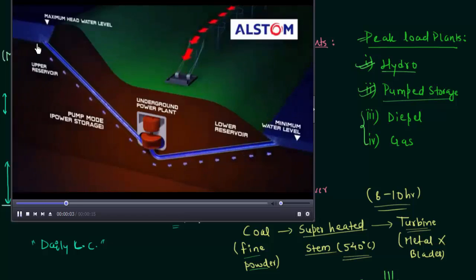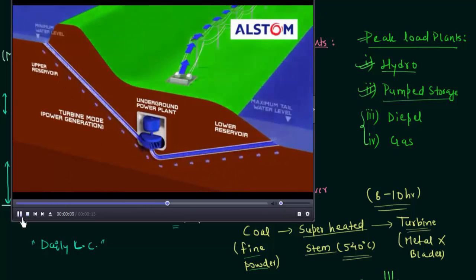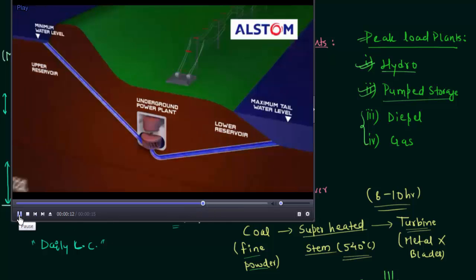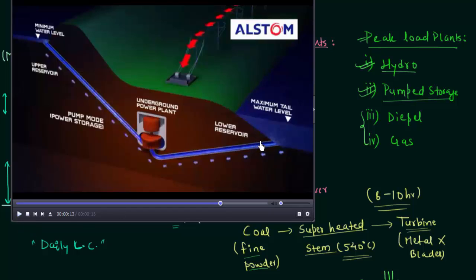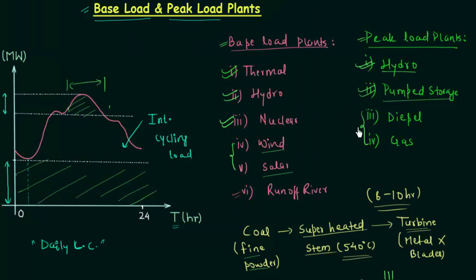In this video you can see the upstream and downstream tanks. During the day when peak load occurs, water flows from the upstream tank through the turbine and is stored in the downstream tank. At night when peak load is gone, the nearby thermal power plant runs the generator as a motor using electrical power, which pumps the water from the downstream tank back to the upstream tank. This allows limited water to be reused repeatedly whenever peak load comes.